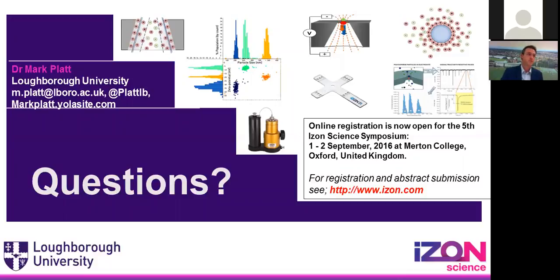In the calibration method, you sample over 100 particles and take the average, and that's your calibration. If the average of those 100 or so particles is quite broad, with a wide distribution, then that will impact the accuracy of the measurements. So a nice tight distribution, small pore sizes, and a calibration particle where the charge matches what you think you have: if you have a negative particle, you want a negatively charged calibration.